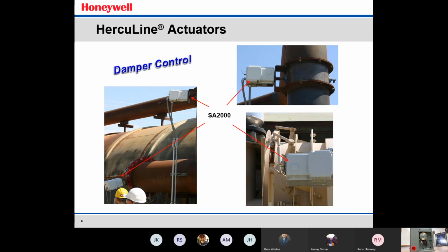Again, a couple more examples. Here's a nice example of a Herculine 2000 with a direct mounted shaft. So not only can these actuators be mounted with a linkage arm, with a crank arm, but it also has an adapter bracket that allows direct coupled actuation to a damper or valve. And that's a pretty good example of it up there on the very top on how you can mount it to a damper.